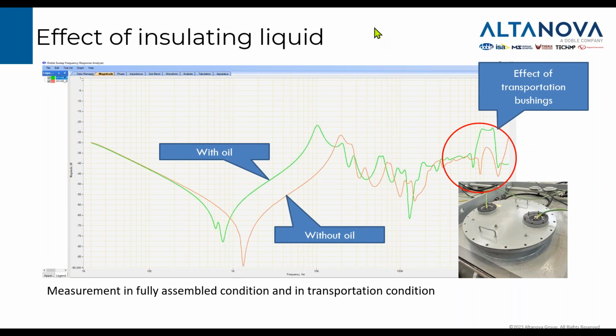Another influencing factor is oil. It can happen that your transformer is drained of oil, and when that's the case, you can expect a horizontal shift between the lines. Here we can see one with the traces shifted to the left, the lower frequency range. This one is with oil, and without oil, it shifts towards higher frequencies. This is because the permittivity of the oil and of the air is different, and this is reflected by our traces, which are built on the RLC network, the winding.